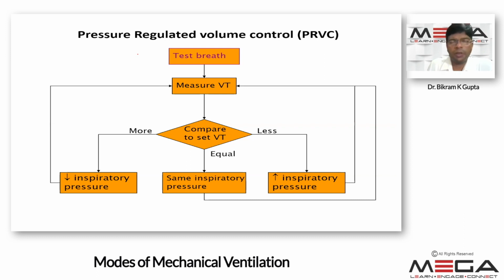So what is the mechanism of pressure regulated volume control? The test breath is given to measure the tidal volume, and the measured tidal volume is compared with the set tidal volume which we have set in the ventilator. If it is equal, the inspiratory pressure stays the same. If the measured tidal volume is less than the set tidal volume, then the inspiratory pressure will increase to try to achieve the set tidal volume. If it is more than the set tidal volume, then the inspiratory pressure will decrease. This cycle goes on, and the ventilator maintains the set tidal volume by increasing and decreasing the inspiratory pressure to maintain the target tidal volume.